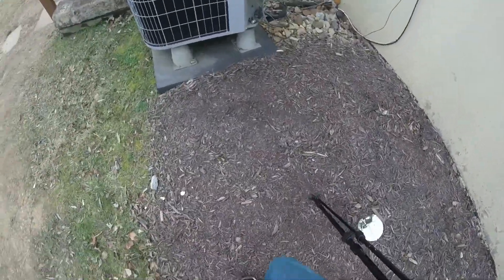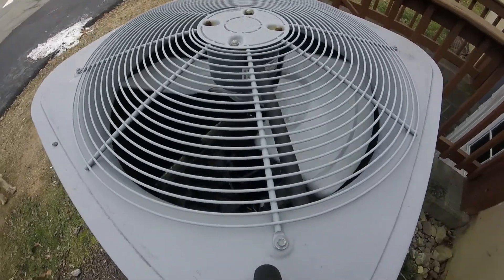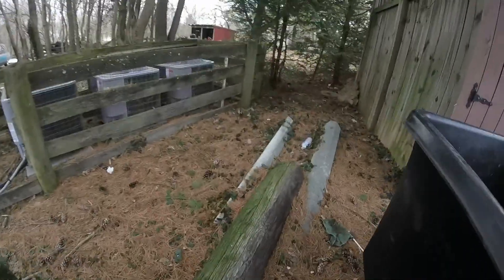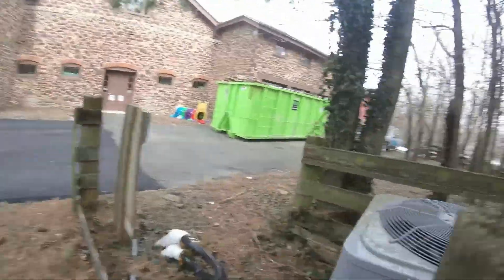Is there ever any water that you found? I haven't seen this thing defrosting other than the time right before I got here, unfortunately. I heard one over there kick into defrost. This one just shut off — it didn't kick into defrost, it just shut off. Some might get shut off here. Check on these one last time. All three of these things are running. This one's a 2020 two-and-a-half ton — it's not a three ton.